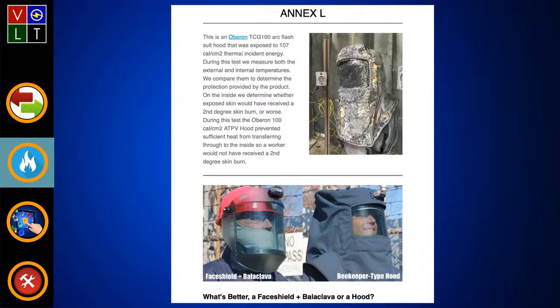Yeah, and he also is wearing safety glasses in that one too. So yeah, that's an interesting point you brought up. So you've got to have that, and you can't let the shield or the hood represent eliminating the safety glasses. Now, notice this moon suit there during an electrical arc condition. You see what happened? Now, up to 12 cal, I can wear the face shield and the balaclava that you see there. But above 12 cal, I've got to go to the moon suit. That's mandatory, and we can find that in 130.7C10. And you'll see that when you download this and go through it if you want to. Go to the next one.